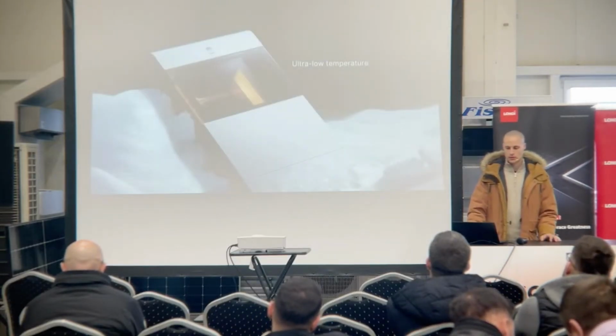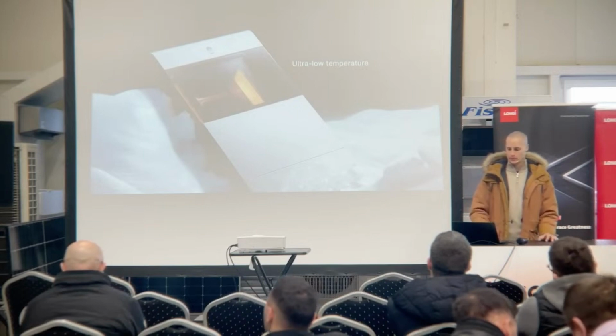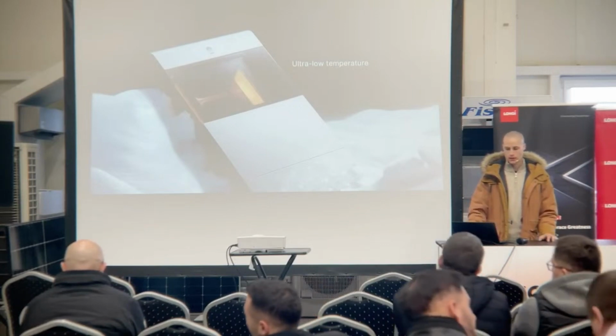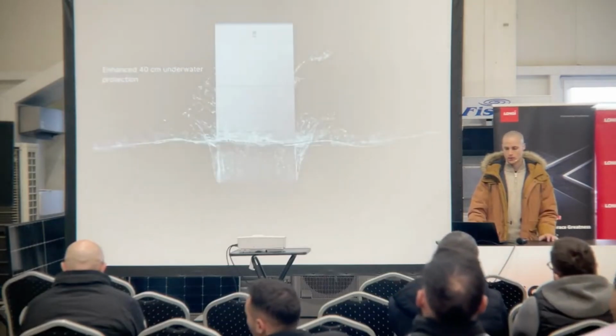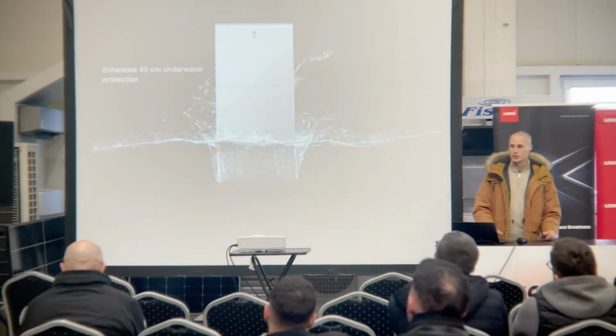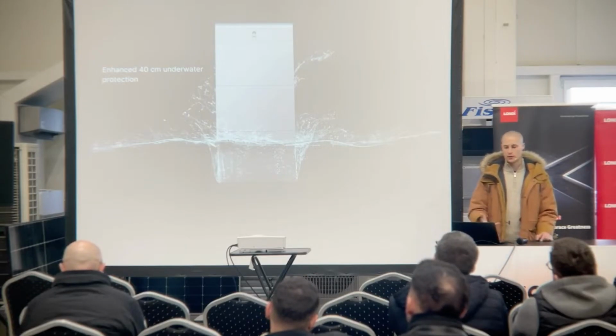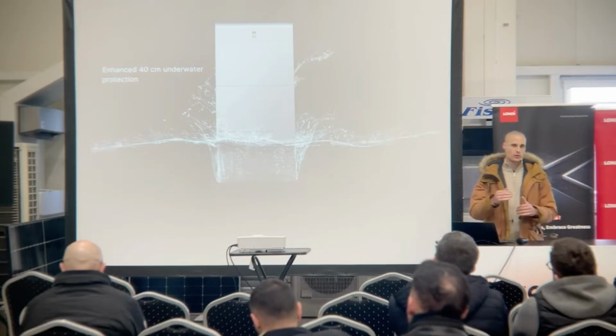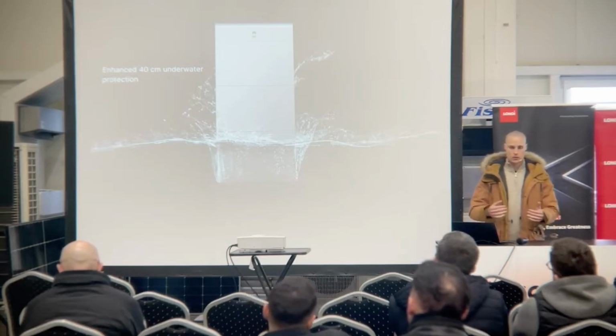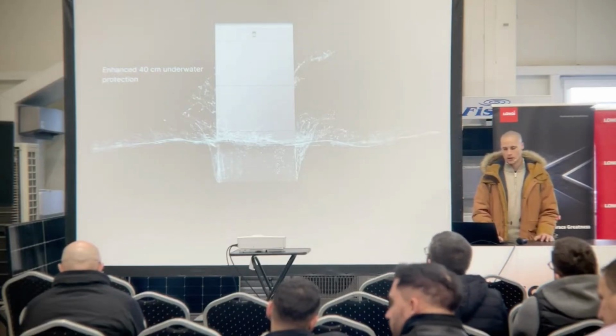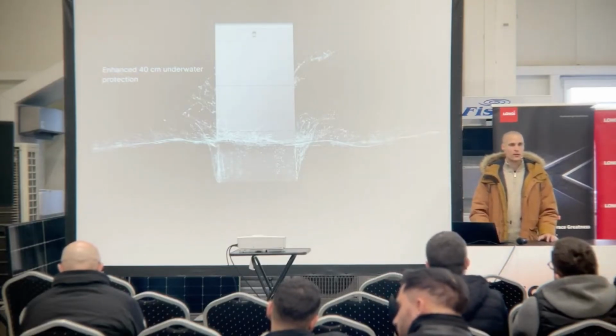Ultra low temperature - just as mentioned, it has heating inside, so like the previous version, it can heat the whole battery pack to maintain a working environment in cold temperatures. Because of the internal connections, if you install it in a basement and there's a chance of flooding, it can withstand 40 centimeters of water, since there are no connections outside of the battery. That's a really good feature for some places, like basement installations.